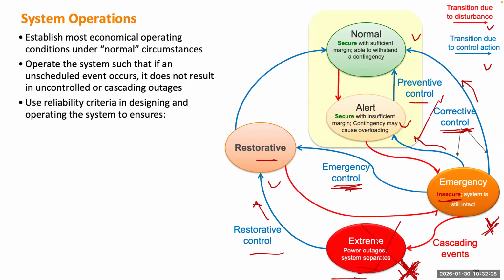Corrective control is still focused on protecting either one piece of equipment or one area, so there's not a large influence on the load or the system operation. But with emergency control, you can just do load shedding. You can trip all the generation or load in one area to protect the rest of the system. That's fine. Then your system will go to the restorative state. Restorative state means the system is not integrated anymore. It can have many pieces running in parallel. Then you need to bring the system back, and eventually it will go back to normal. So that's a very important diagram to show what the operator is operating, how to look at the system, and how the operator can operate the system among different situations.